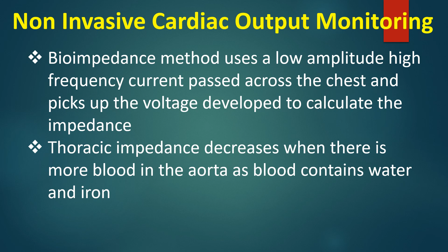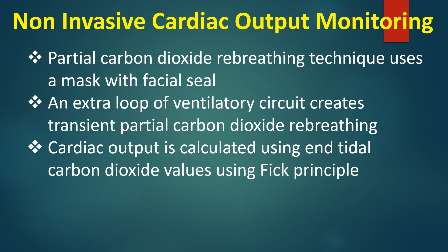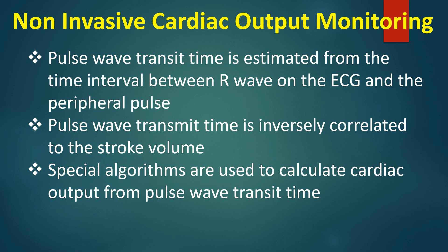Partial carbon dioxide rebreathing technique uses a mask with facial seal. An extra loop of ventilatory circuit creates partial carbon dioxide rebreathing. Cardiac output is calculated using end-tidal carbon dioxide values using Fick's principle. Pulse wave transit time is estimated from the time interval between R wave on the ECG and the peripheral pulse. Pulse wave transit time is inversely correlated to the stroke volume. Special algorithms are used to calculate cardiac output from pulse wave transit time.